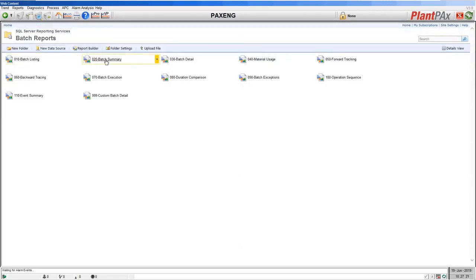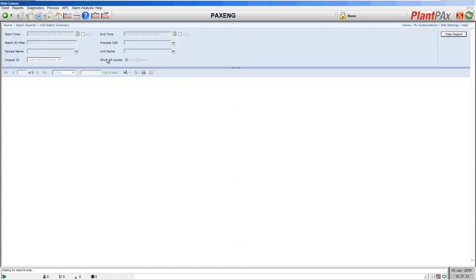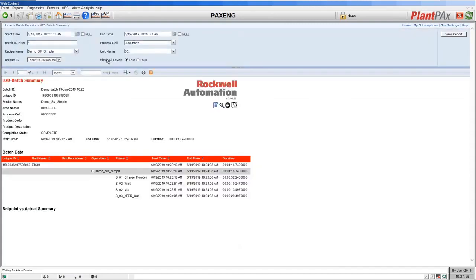Let's go back to our list of reports and look at the batch summary. This is a summary report of a particular run of a Sequence Manager sequence. Here you can see header data showing the batch ID we assigned, the unique ID the system assigned to the execution, the recipe name which is the name of our Sequence Manager program in the controller, the start and end times, durations, and for each equipment phase that ran: the start and end times and how long they took.